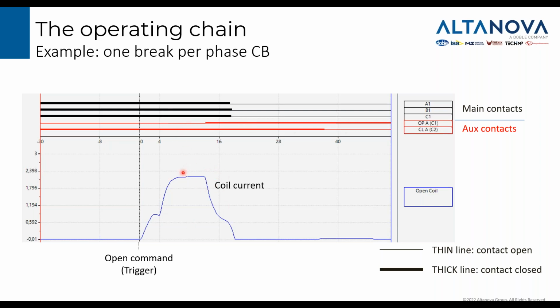Here you see the profile of the coil currents during the operation. It starts from 0, it reaches a maximum, and then returns down to 0. The operation time is measured from the moment that the coil is energized. So from the moment where the current starts to be higher than 0.